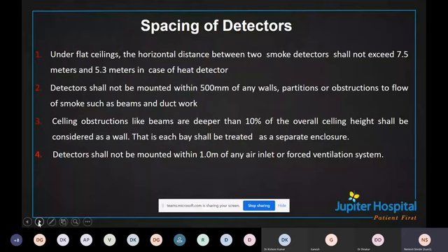Now, if you see the detectors, there is always a question of what should be the distance between two smoke detectors. Two smoke detectors shall not be more than 7.5 meters apart. These are the normal norms which we need to consider while spacing the detectors. Under any flat ceiling, the horizontal distance is 7.5 meters between two smoke detectors and 5.3 meters in the case of heat detectors. Now, detectors shall not be mounted within 500 mm of any wall.